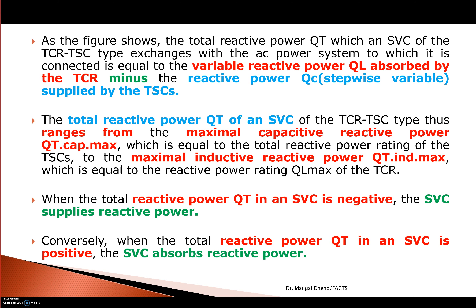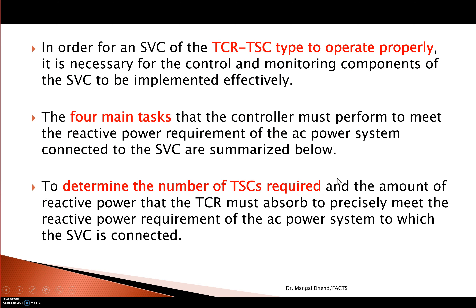QT can be varied from maximum to minimum. Net power QT equals QL (maximum TCR supply) minus QC. The rating of TCR in TCR-TSC will be less compared to TCR-FC. To operate it smoothly, four main tasks are required: finding the number of TSC required, switching TSC in and out via firing angle control, determining TCR firing angle for the required power, and coordinating control of both TCR and TSC.